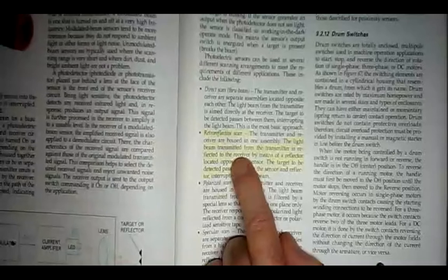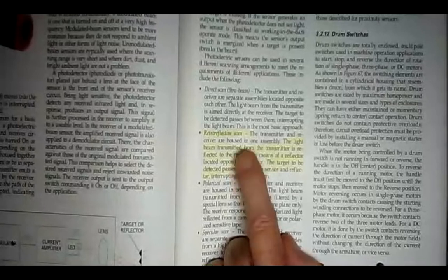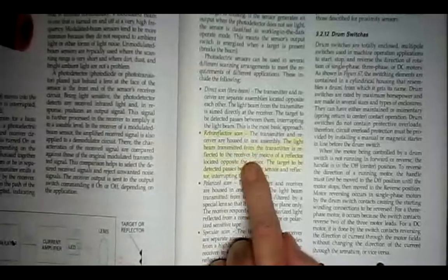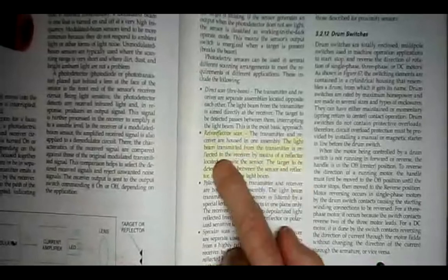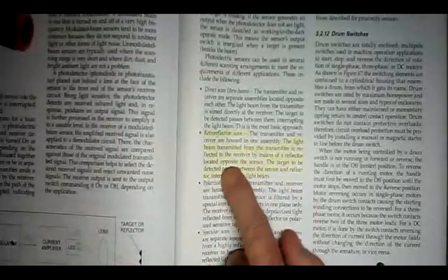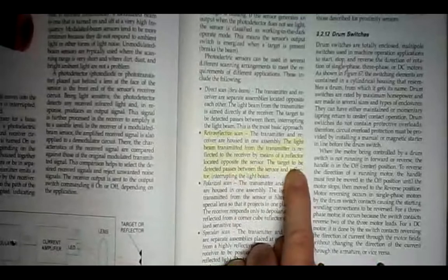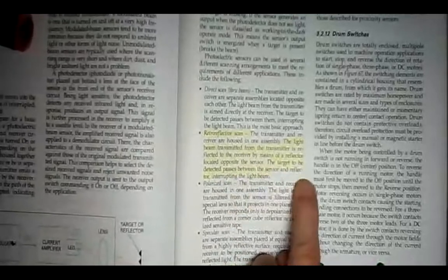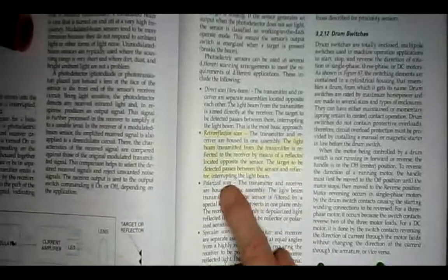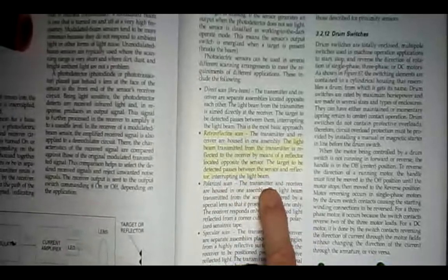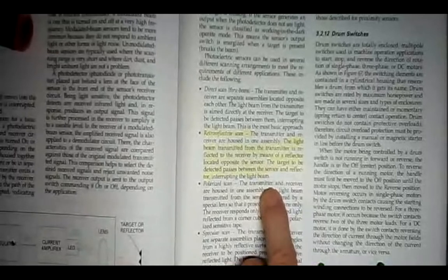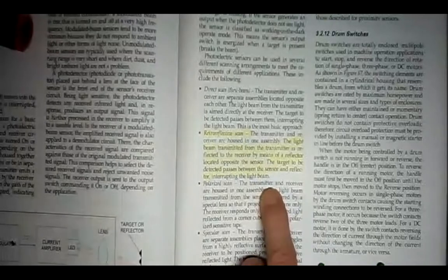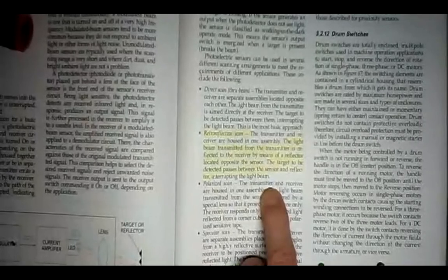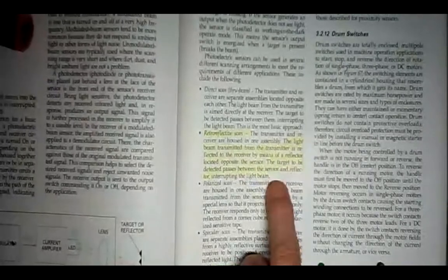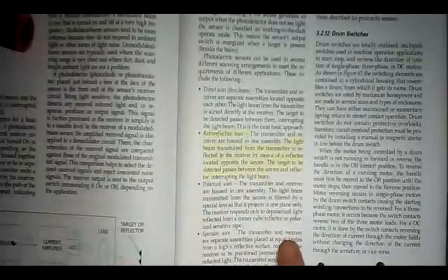This one, you only have to take power to one side because both the sending unit and the receiver are in the same device. Retroreflective scan, the light beam transmitted from the transmitter is reflected to the receiver by means of a reflector located opposite the sensor. The target to be detected passes between the sensor and the reflector, interrupting the light beam. But the sending unit and the receiver are mounted on one side of the conveyor, so you only have to power up one side. The other side is just a reflector. Okay.